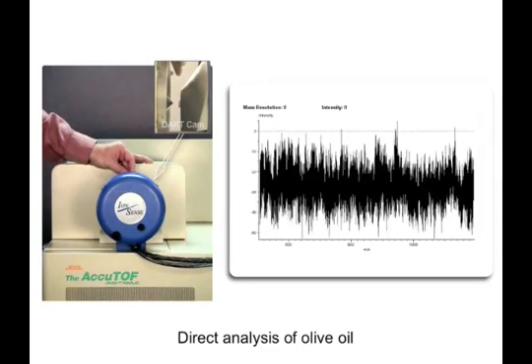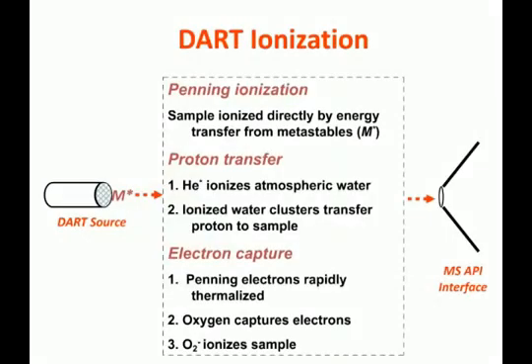So we can probably go ahead and stop the video right there. And then we'll resume by talking about how DART ionization works. DART ionization is based on Penning ionization, a term originally developed by F.W. Penning in 1927, where they discovered that excited-state neutrals can produce an ion and electron if they come in contact with a sample that has a lower ionization energy than the energy of the neutral. So the first step in DART ionization is the Penning ionization, where the sample is ionized directly by energy transfer from long-lived excited-state neutrals, or as we call them, metastables.